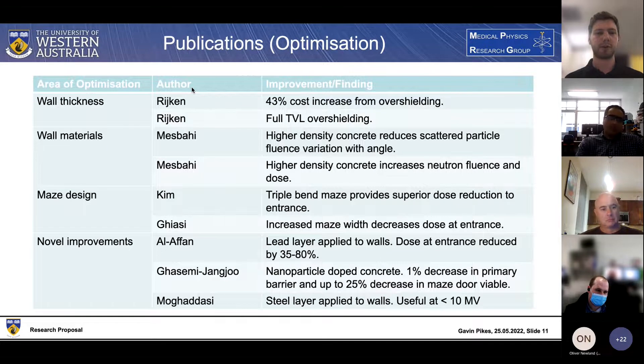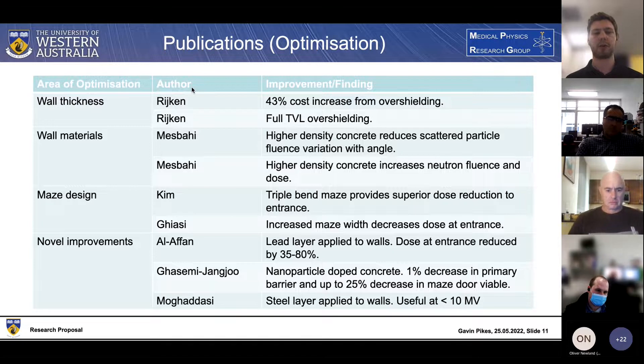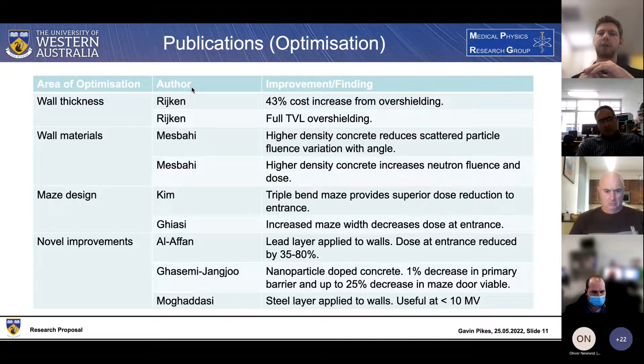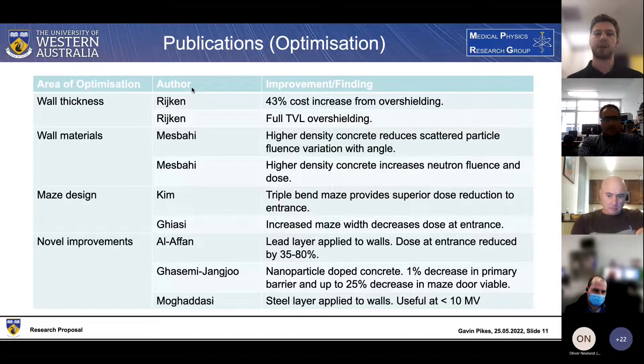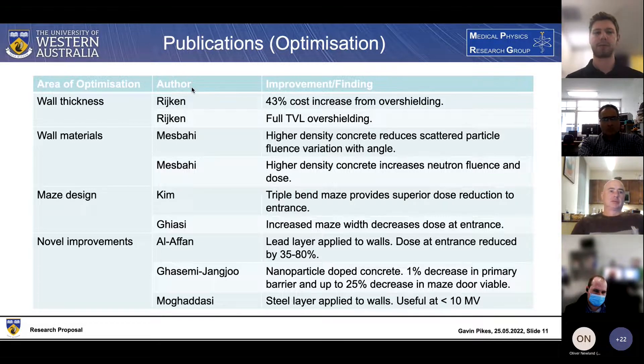In terms of optimization publications, there are four main areas: wall thickness, wall materials, maze design, and novel improvements. Rijken in particular has put a lot of effort into examining wall thicknesses regarding NCRP recommendations. In one paper examining 75 different bunkers being built, he found that a 43 percent cost reduction could be made just by removing overly conservative values used to determine shielding. For a bunker around the size of the MARY linac bunker, this equates to about a $340,000 AUD saving.